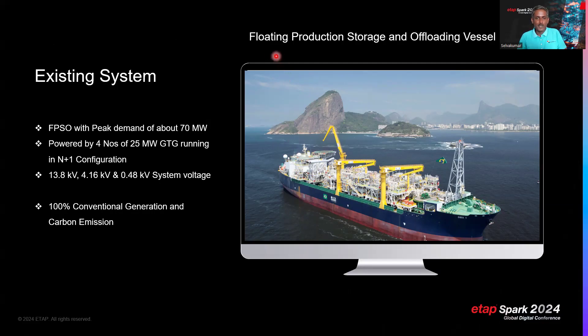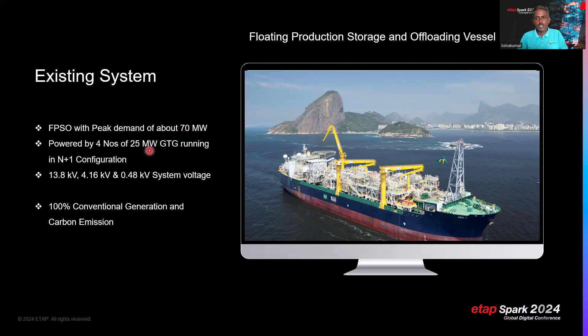FPSO stands for Floating Production Storage and Offloading vessel. From an electrical perspective, this existing system has a peak demand of 70 megawatts. It is powered by four 25-megawatt gas turbine generators running in an N+1 configuration, meaning even if only three of the four generators are running they can still meet the 70-megawatt peak demand.